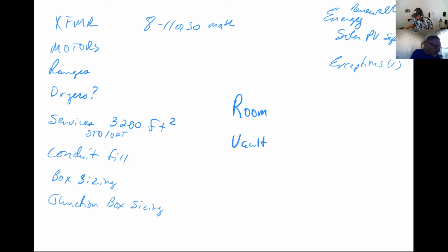So page 335, it's 450.21(b). They tell you in that section, on the right-hand side of page 335, anything that's 112 and a half needs to be in a room, and the room is rated at 1 hour. 1 hour is a pretty basic fire rating for construction materials - if it's got any fire rating at all, it's almost always a minimum of an hour anyway, so that's pretty easy to do.